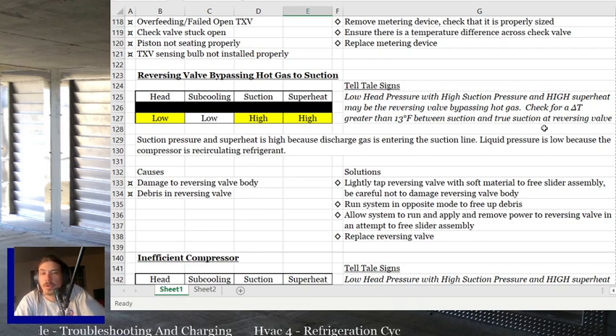Again, generally no more than 3 degrees across any component. The reversing valve is an exception. I've seen different numbers here. I've seen 8, I've seen 7, I've seen 13. I just go with 13 because it's the biggest one I've seen. It's guaranteed. If it's over 13 degrees, you're bypassing hot gas. It could be less than 13 degrees and you still might be bypassing some, but it's probably not enough to really cause an issue. But if it's over 13 degrees, guaranteed it's causing a problem.